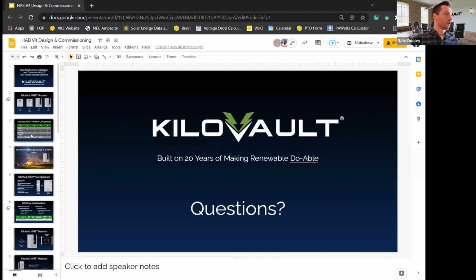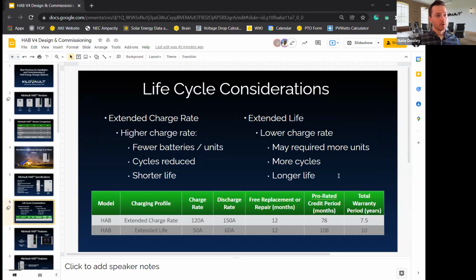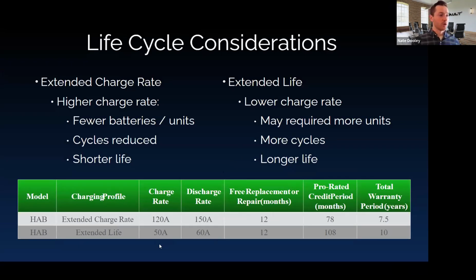This goes back to our initial discussion on charge rate. If you think about inverter size in terms of discharge rate, you could calculate the max discharge rate of the inverter by roughly dividing its maximum continuous output by the battery voltage. For example, a 6,800 watt inverter discharging at about 54 volts nominal for the HAB: 6,800 over 54 is about 125 amps. That puts you in the top category, maybe even pushing it a bit for a single HAB bank.